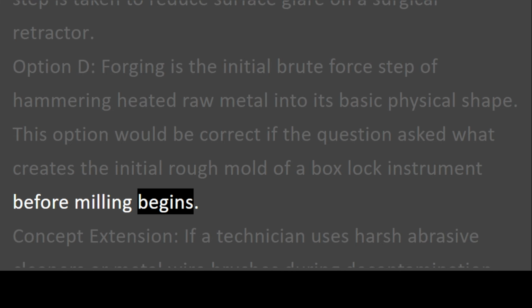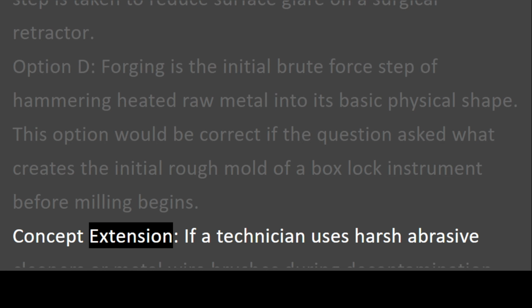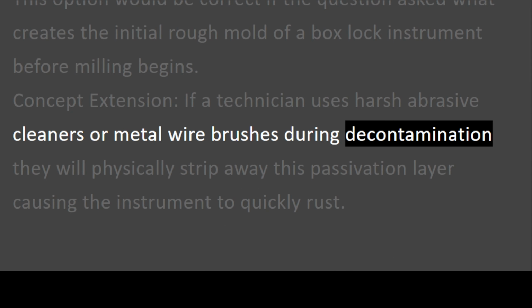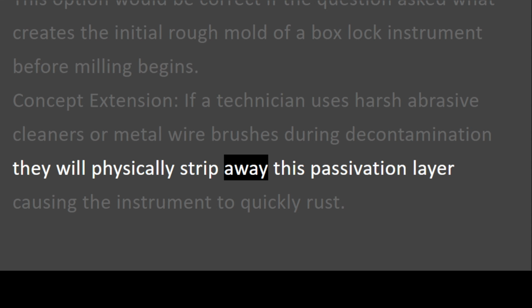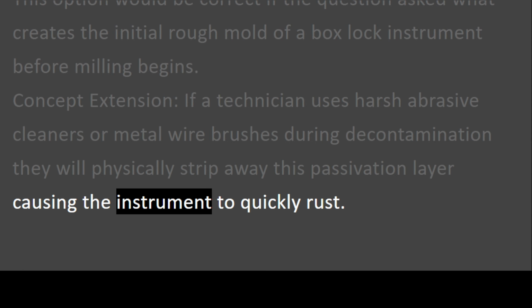instrument before milling begins. Concept extension. If a technician uses harsh abrasive cleaners or metal wire brushes during decontamination, they will physically strip away this passivation layer, causing the instrument to quickly rust.